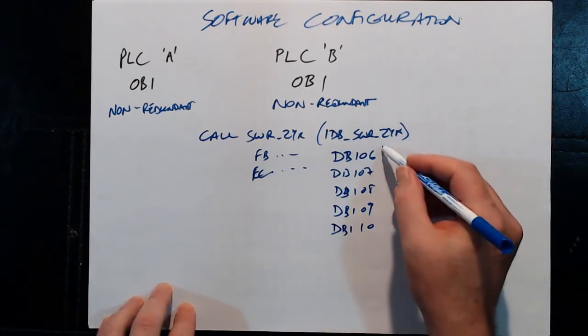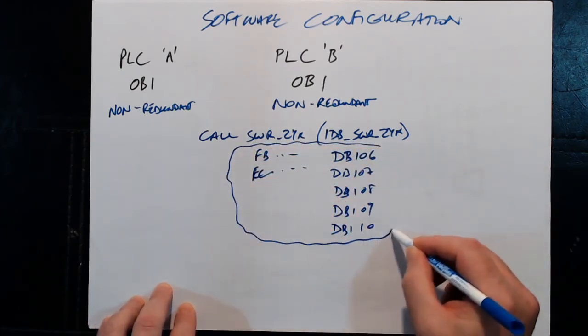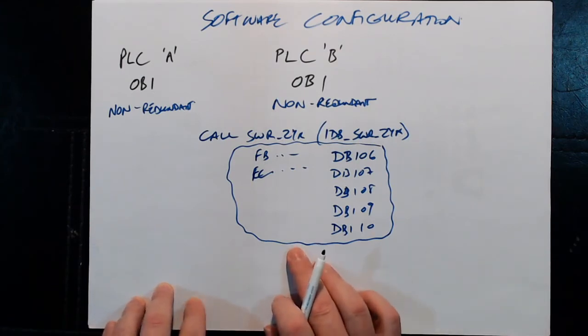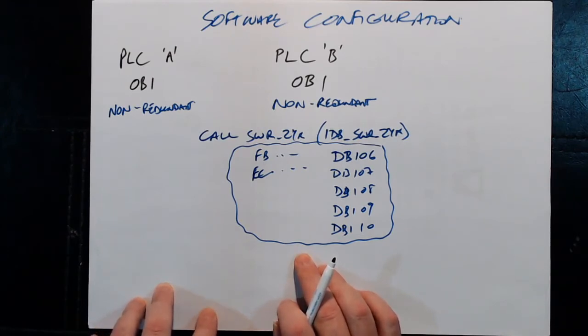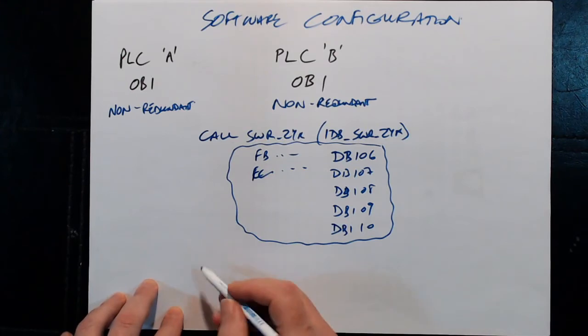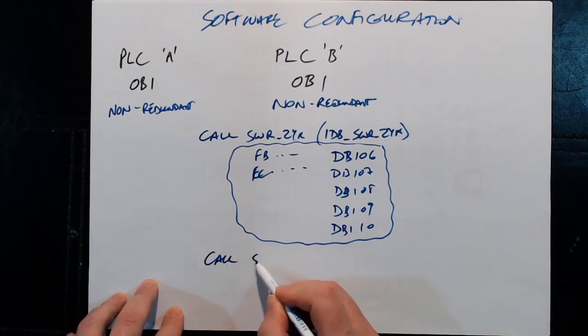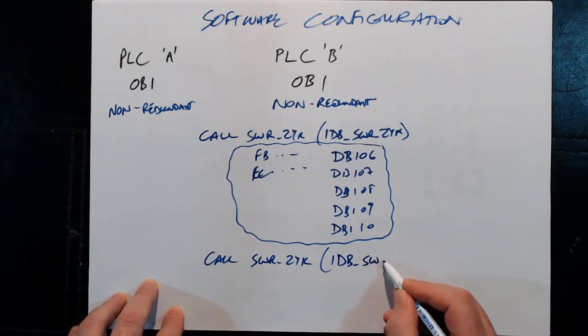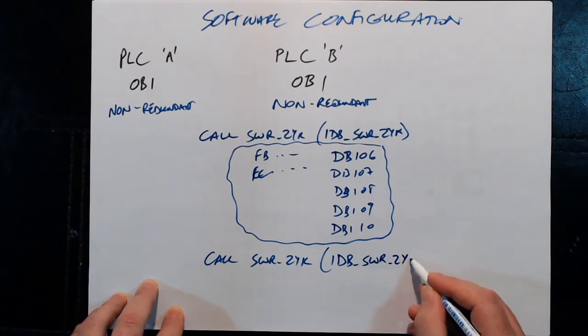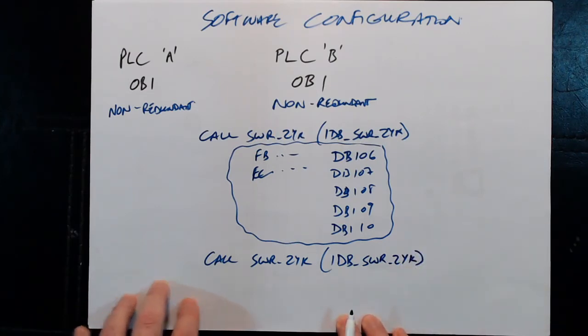So this is all part of the redundant program. And this will be called in one of the two PLCs, whichever one is in control of the outputs, whichever one is calling itself master at that time. At the end, we do another call to the same function block, and we call the same instance DB. This is a little bit different to what you normally see in a normal PLC, because typically you don't call the same function block with the same instance DB in two different places. But for this specific application you do.